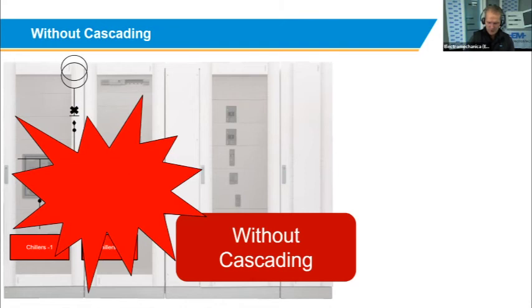So instead of just losing the power supply to the installation, you might lose your whole board. You've got a shutdown period. You need to replace the products, you need to replace the board. And instead of a quick reset of one product, you're now sitting without a board, maybe for a day or two, whatever the case may be, to fix this. And the cost involved is huge, in replacing all of this, and the manufacturing part of it is you lose manufacturing capability. So that is the difference between discrimination and a cascaded system.